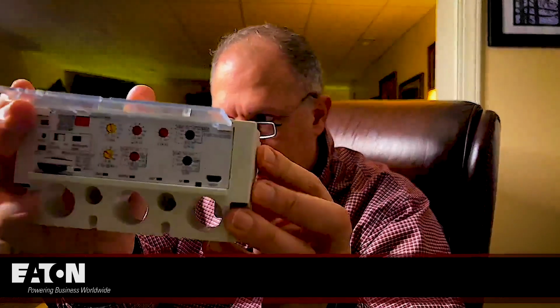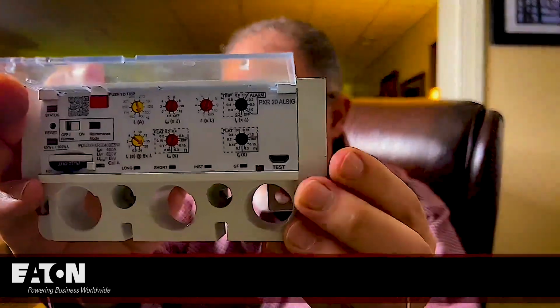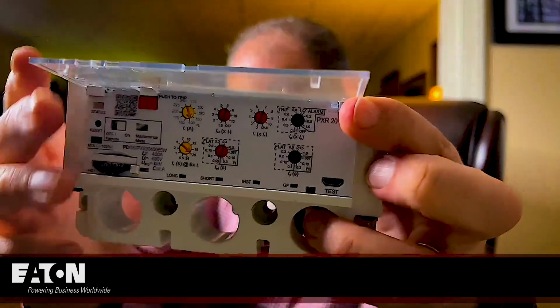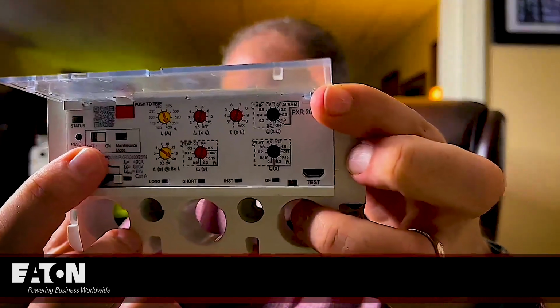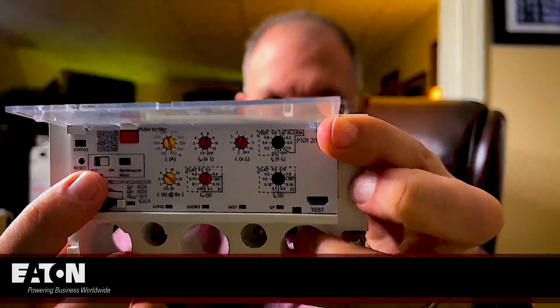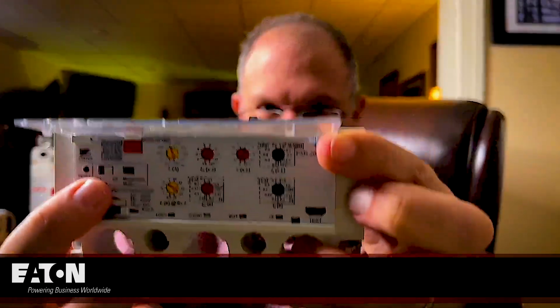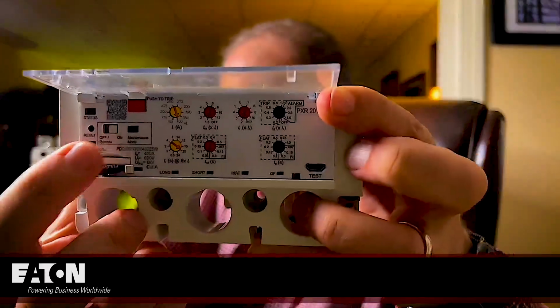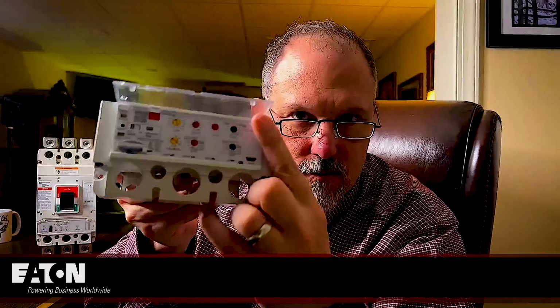This is a PXR20. So now the PXR20 has an arc reduction maintenance switch. It has one right there. That's the arc reduction maintenance switch. Notice all of the other interfaces, these are just rotary dials that adjust the settings on how fast this responds to currents that pass through.